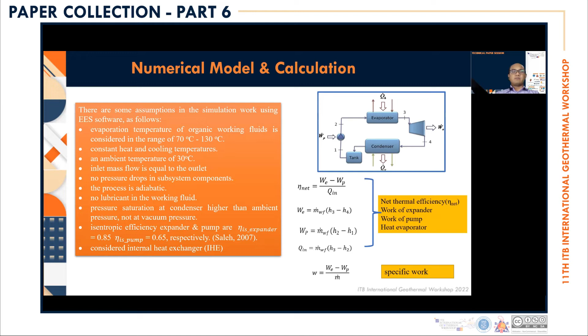Isentropic efficiency of the expander is 0.85 and of the pump is 0.65, and then consider an internal heat exchanger. Using the Engineering Equation Solver, the mass and heat balance model of the ORC is stated by these equations. The system net thermal efficiency, work of expander, work of pump, total heat of evaporator, and specific work have been calculated.